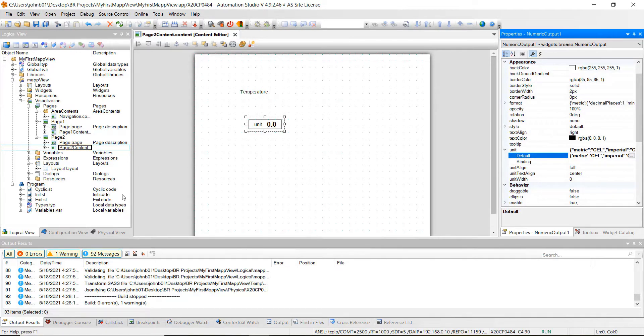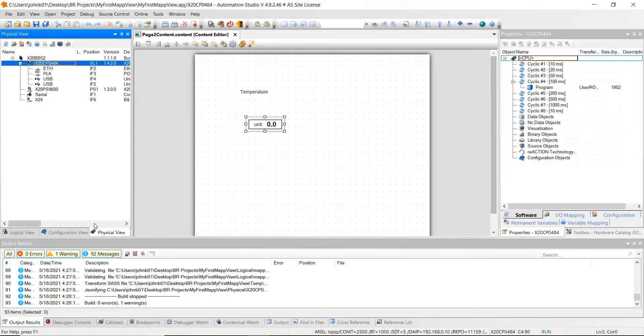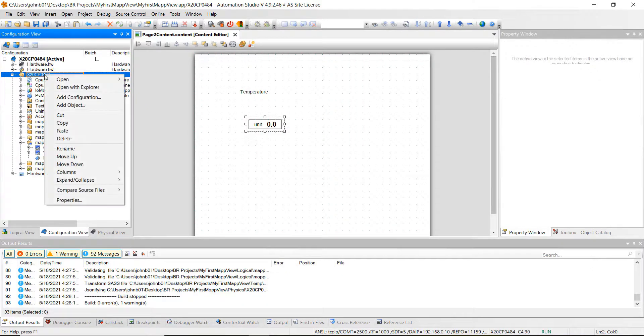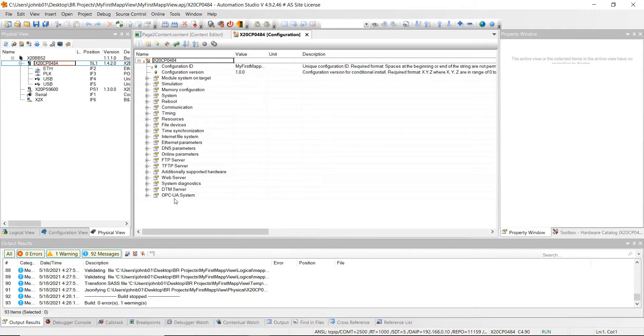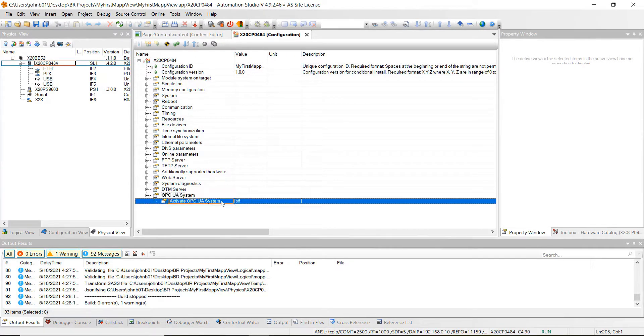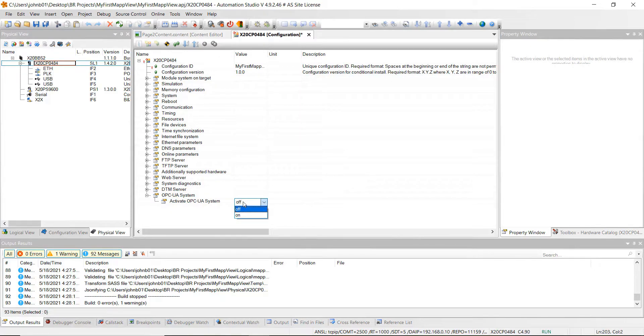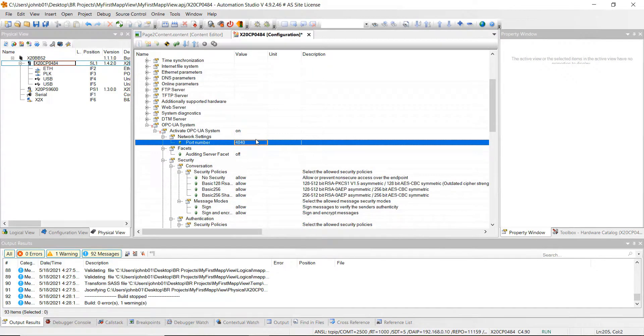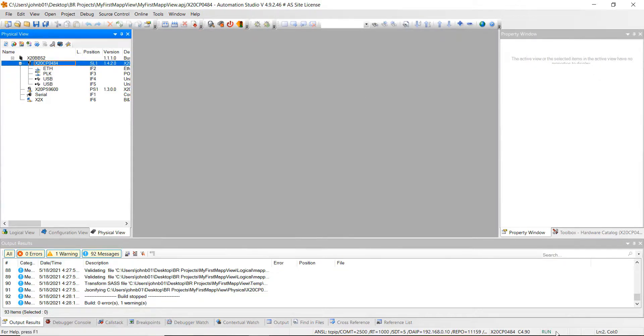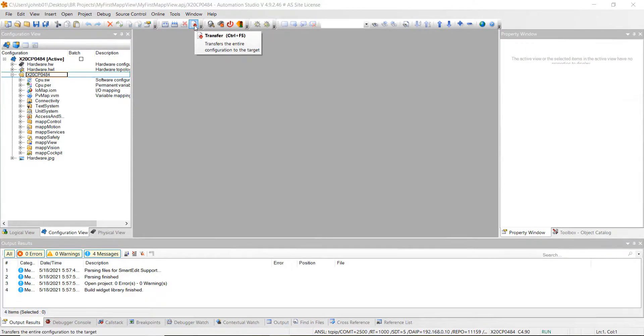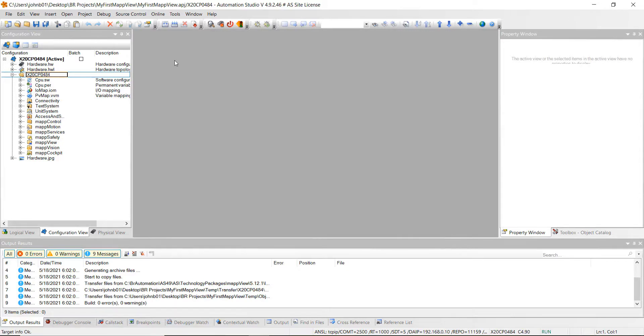One last critical step I forgot to mention: we need to go to the physical view, and under the CPU go to the configuration view. Go down to the OPC UA system and explode that. We need to activate this - right now it's off. If it's not on, all this OPC UA stuff we did is not going to work. Go ahead and click on, leave the port number the same, and hit save all. Then close this and we should be good to go. Let's go ahead and transfer the project. Make sure we're in run mode and connected with our controller, then hit transfer.